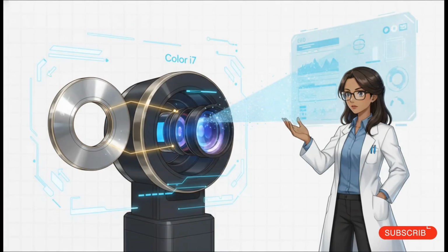And here is where the hardware and software really talk to each other. When you swap that magnetic aperture plate and select it in your software, the Color i7 has a self-adjusting zoom lens that automatically moves to synchronize with your new aperture size. It completely eliminates configuration errors, which is huge. Plus, your software completely controls whether your measurement is specular included or excluded. Or actually, you can even do both simultaneously. And lastly, the instrument has an automated 400nm UV filter. You can fully exclude UV or calibrate it using a provided checker to perfectly match D65 daylight.